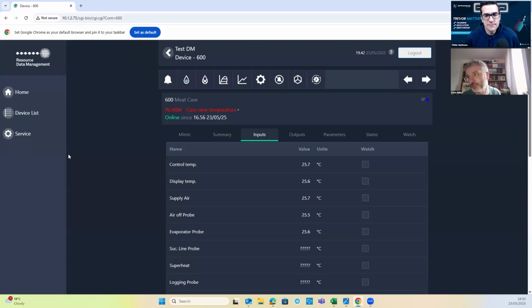When it's on defrost, I'm checking my defrost termination probes and met the temperature, because if it's terminated on time, I'm asking myself, why is it terminated on time? Why has it not made the temperature? Have I put too high a temperature in? Is the valve not shut? And I can check my evaporator temperature for that. My probe, regardless of whether I'm using a transducer or not, that probe's still on the inlet.